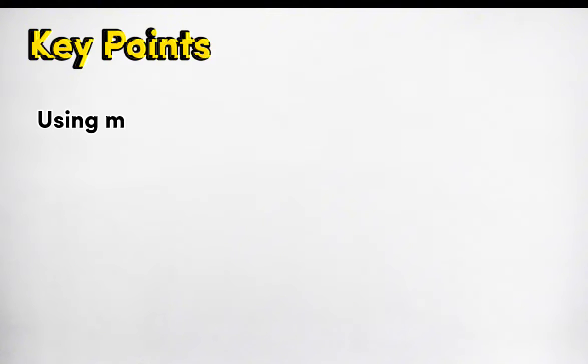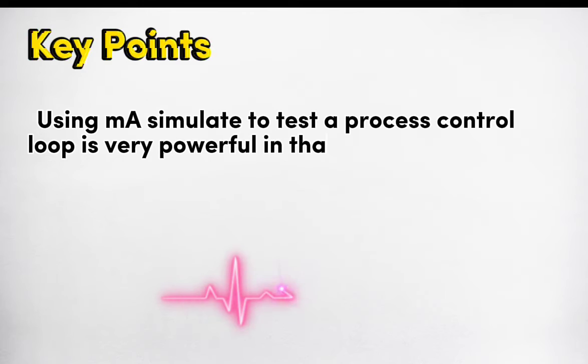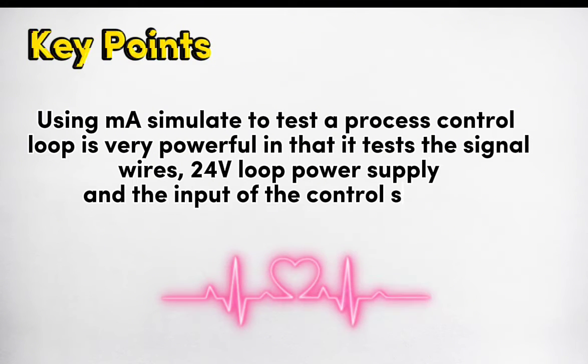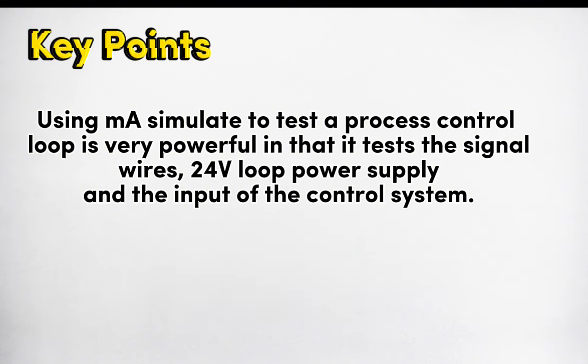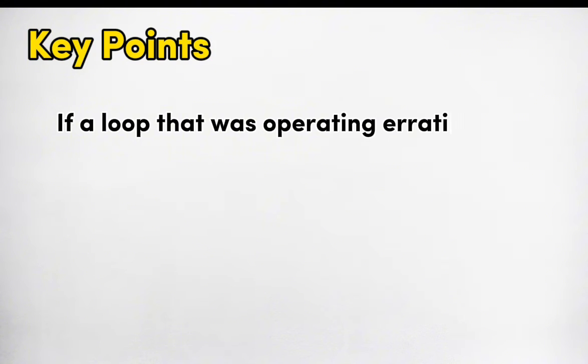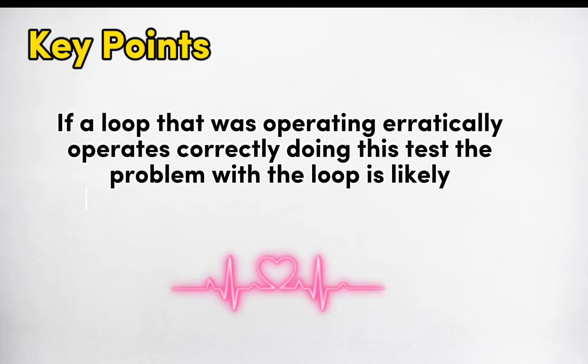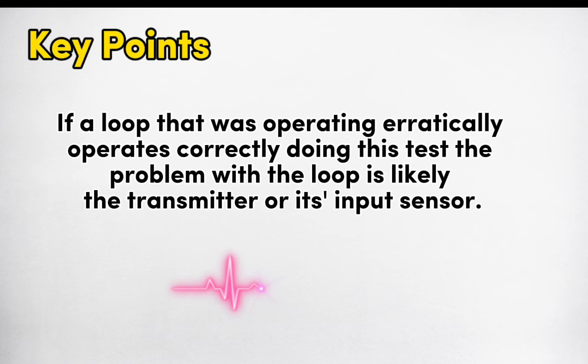Using milliamp simulate to test a process control loop is very powerful in that it tests the signal wires, 24-volt loop power supply, and the input of the control system. If a loop that was operating erratically operates correctly during this test, the problem with the loop is likely the transmitter or its input sensor.